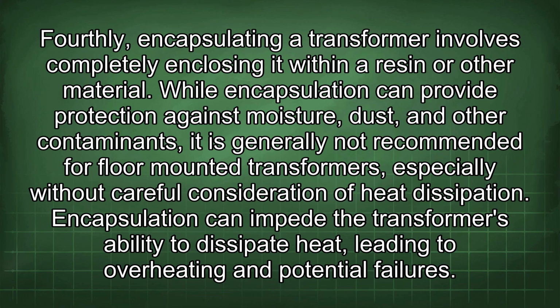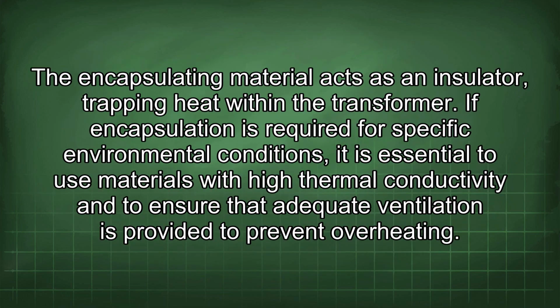dissipation. Encapsulation can impede the transformer's ability to dissipate heat, leading to overheating and potential failures. The encapsulating material acts as an insulator, trapping heat within the transformer. If encapsulation is required for specific environmental conditions, it is essential to use materials with high thermal conductivity and to ensure that adequate ventilation is provided to prevent overheating.